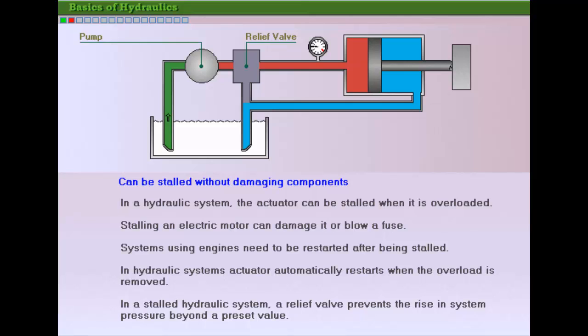In the given example, when the actuator stalls, system pressure rises. The relief valve opens and diverts the fluid back to the reservoir as long as the overload condition remains.